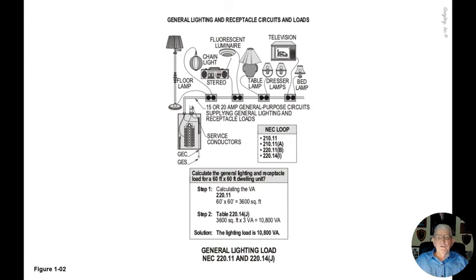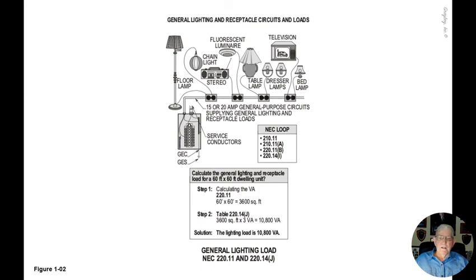The requirement is to calculate the general lighting and receptacle load for a 60 by 60 square foot dwelling in accordance with 220.11. In Step 1, we calculate the VA and apply 220.11 by taking 60 by 60 square feet times 3 VA per square foot. In Step 2, that equals 10,800 VA. So after reviewing Step 1 and Step 2, the total VA for the lighting load and receptacle load is 10,800.